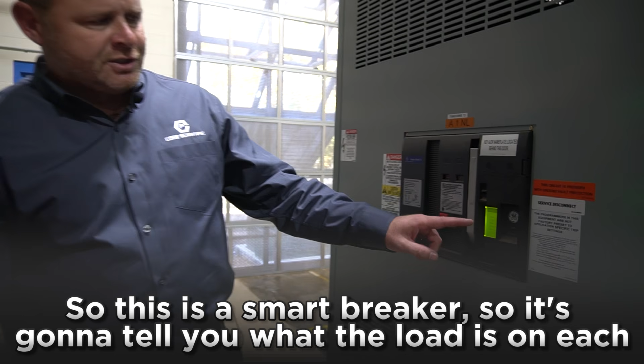Smart breaker, so it's going to tell you what the load is on each piece of 4,000 amp switchgear. You see we've built the venting out the top so that the heat - feel this, go ahead and put your hand up here and feel this. See the heat that comes out of it? That venting is sucking all that heat up off the breakers, and we do that so we can keep our uptime as close to 100% as possible.